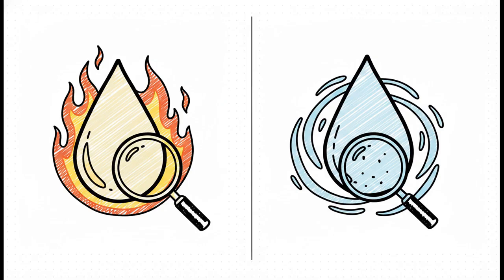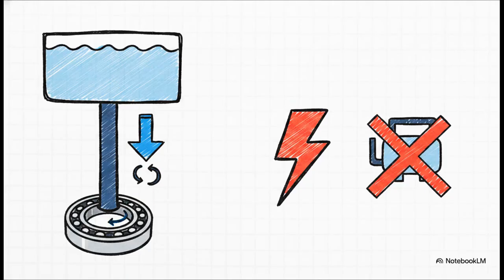Treat them as two entirely different risk profiles. So, what happens to those bearings if your plant suffers a total blackout? Well, the AC power dies, meaning your main lube pumps instantly shut off. But that massive generator rotor, it has so much inertia, it's still coasting down from 3,600 RPM. Without oil, it would tear its own bearings apart in seconds. That's exactly why we have overhead rundown tanks. Honestly, it's a beautifully dumb mechanical backup. Pure gravity just feeds stored oil straight down into those bearings during the coast down. No electricity needed whatsoever. When the lights go out, physical gravity beats a smart electrical system every single time.